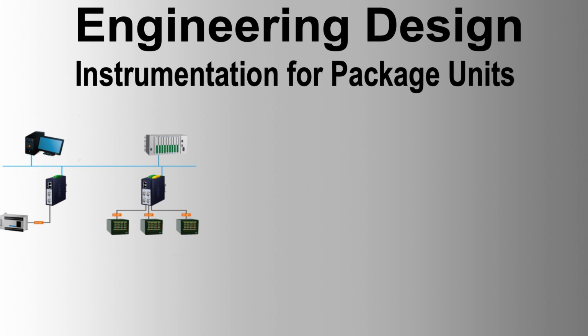Communication to the plant's DCS, communication between the packaged unit control system and IPS logic solver, and the plant DCS shall be implemented via galvanically isolated serial communication links using the Modbus RTU protocol. Redundancy requirements shall be indicated in the requisition.